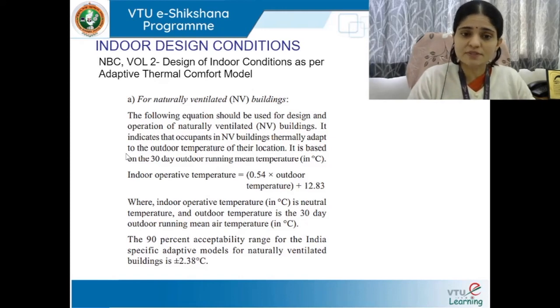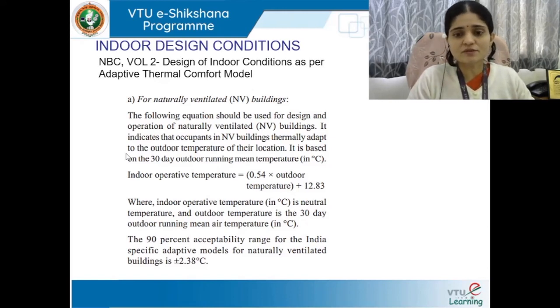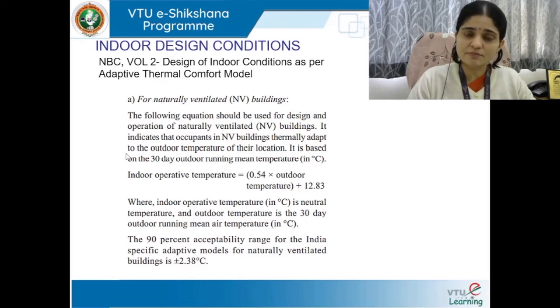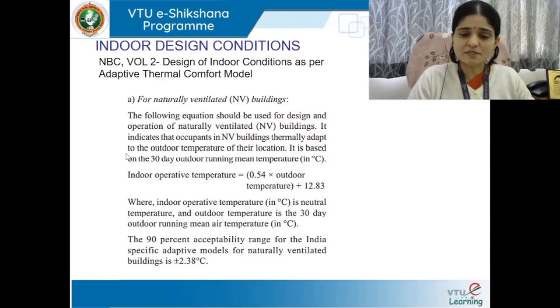The following equation should be used for design and operation of naturally ventilated buildings: occupants in naturally ventilated buildings thermally adapt to the outdoor temperature of their location — that is a human physiological tendency. It is based on the 30-day outdoor running mean temperature. The indoor operative temperature equals 0.54 into the outdoor temperature plus a factor of 12.83. The 90% acceptability range for India-specific adaptive models for naturally ventilated buildings is around plus or minus 2.38 degrees Celsius.